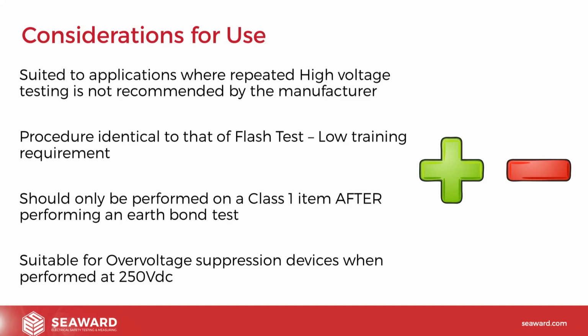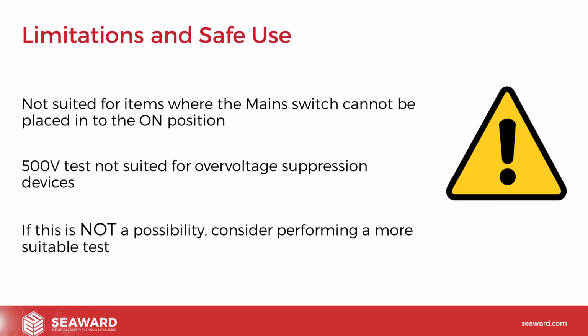And as we previously mentioned, this test is suitable for overvoltage suppression devices. So again, surge protected extension leads, if it's performed at 250 volts. But what about limitations and any safety considerations? Well, as we said, whilst it's useful in circumstances where the manufacturer may not apply the high voltage, it does have limitations. It's not suitable for testing at 500 volts where surge protection is prevalent. Again, we're going to fall into the same trap of getting potential false failures.